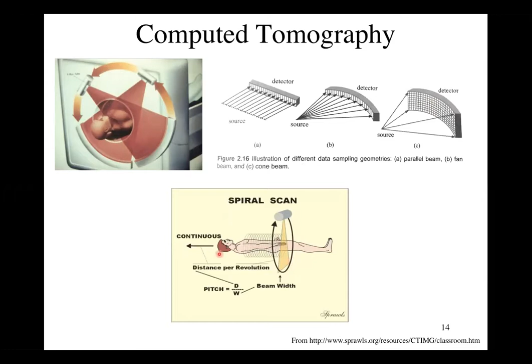Another trick in modern CT scanners is you can continuously rotate this source and detector pair while moving the patient continuously through that beam of X-rays to get a large field of view X-ray image or a volume X-ray image. You can imagine if I have a very thick detector like this, and so I'm getting a very thick amount of data each time, I can move the patient through there very quickly and still achieve all of my data.